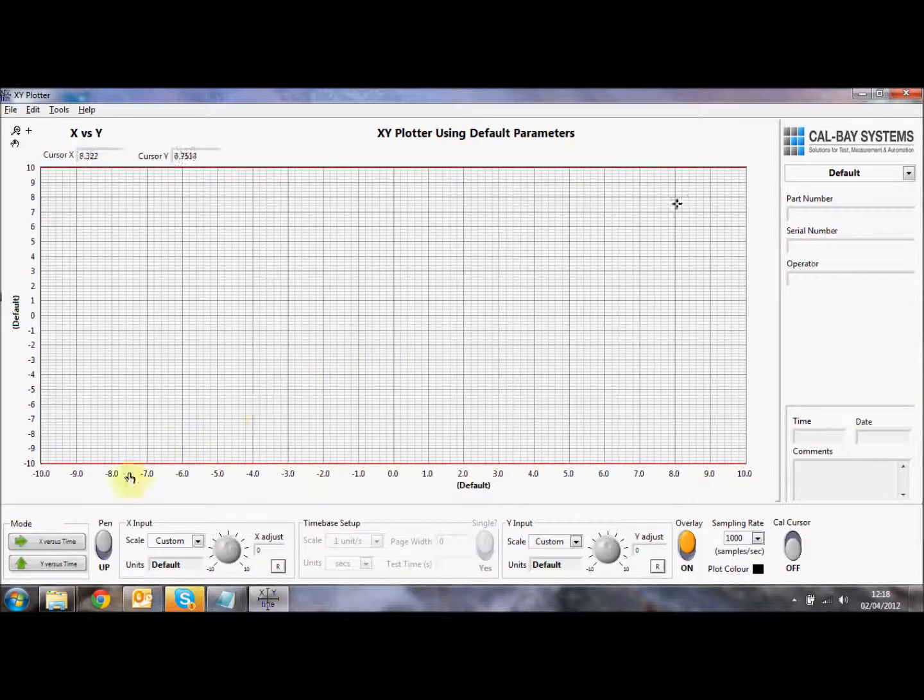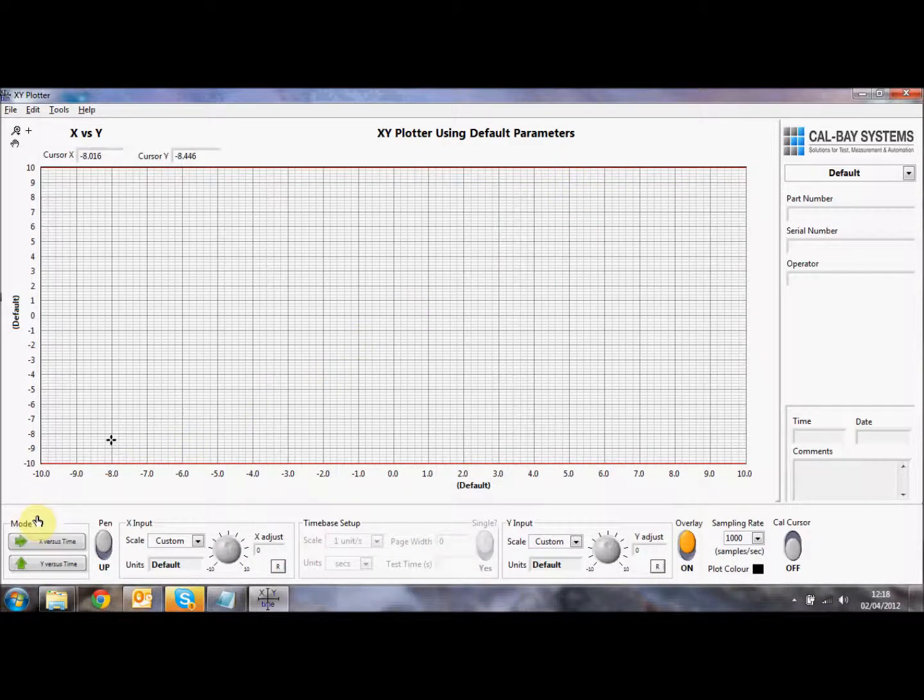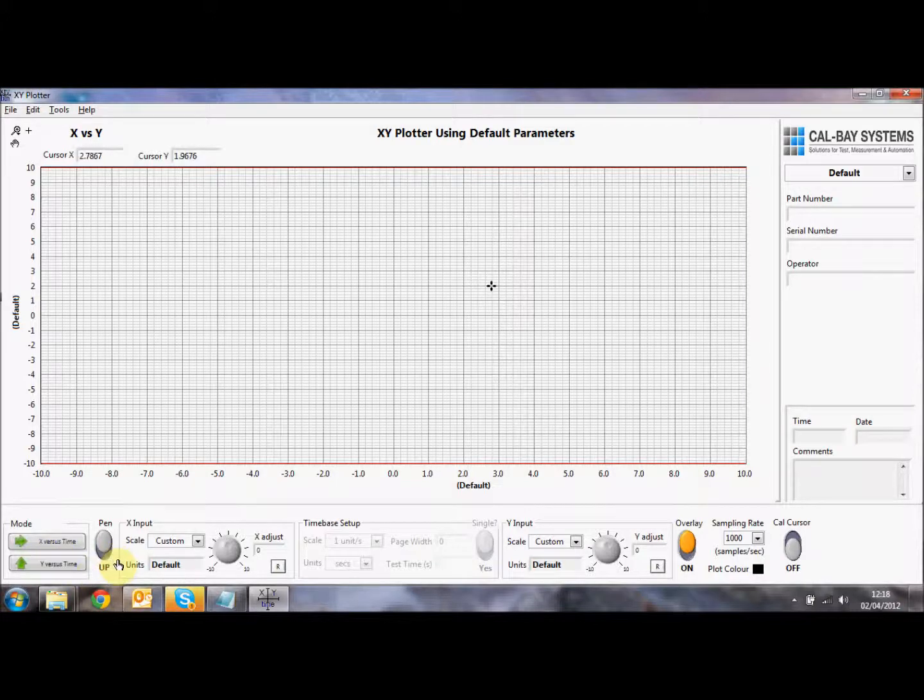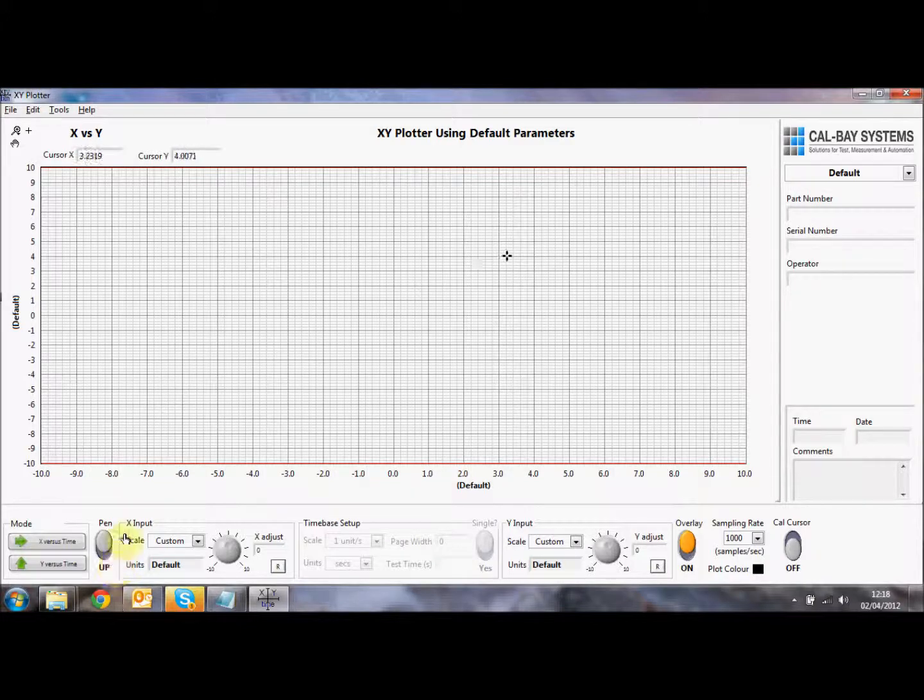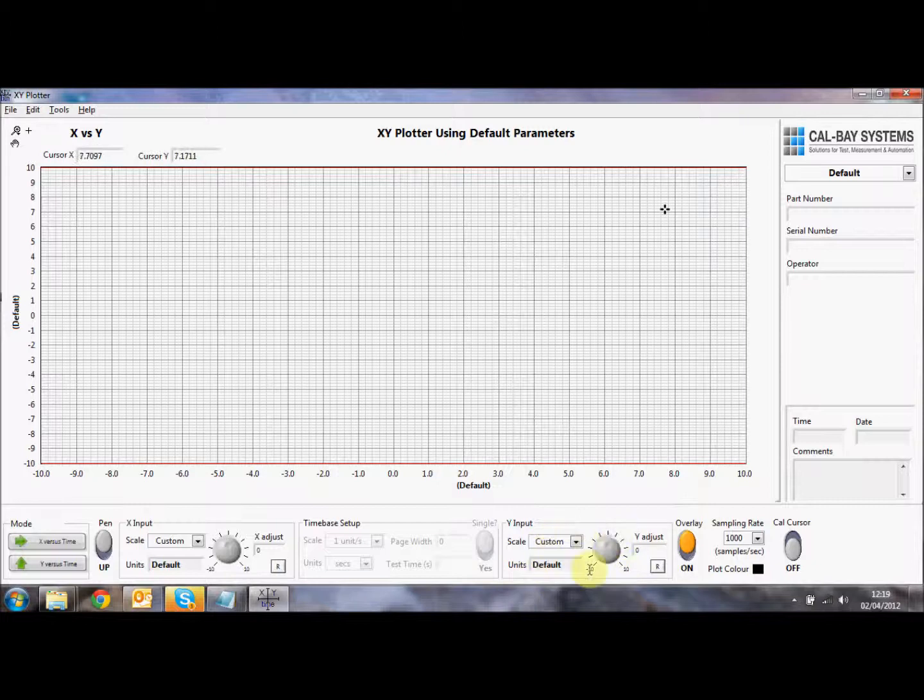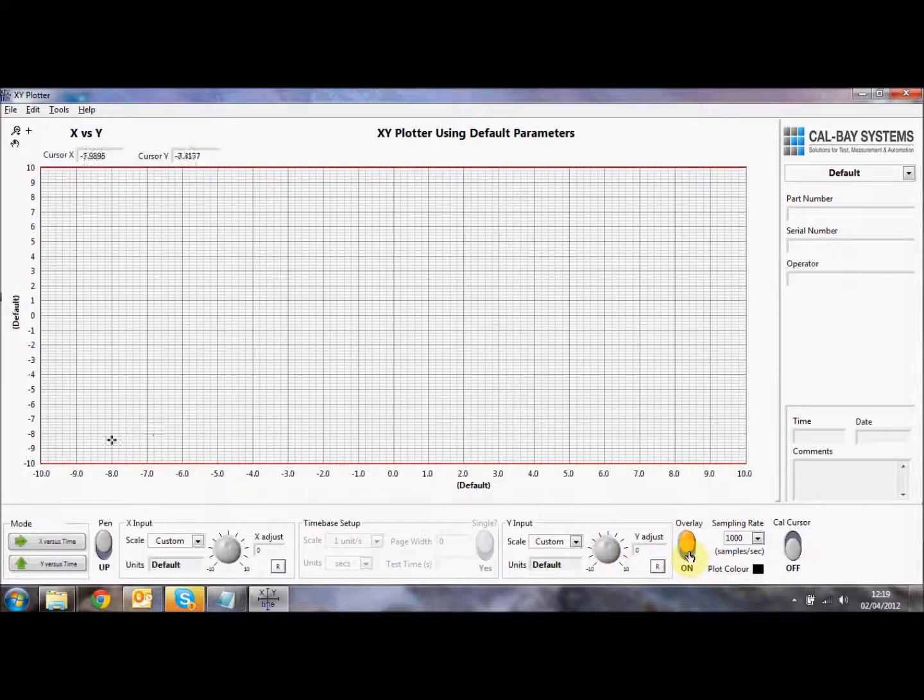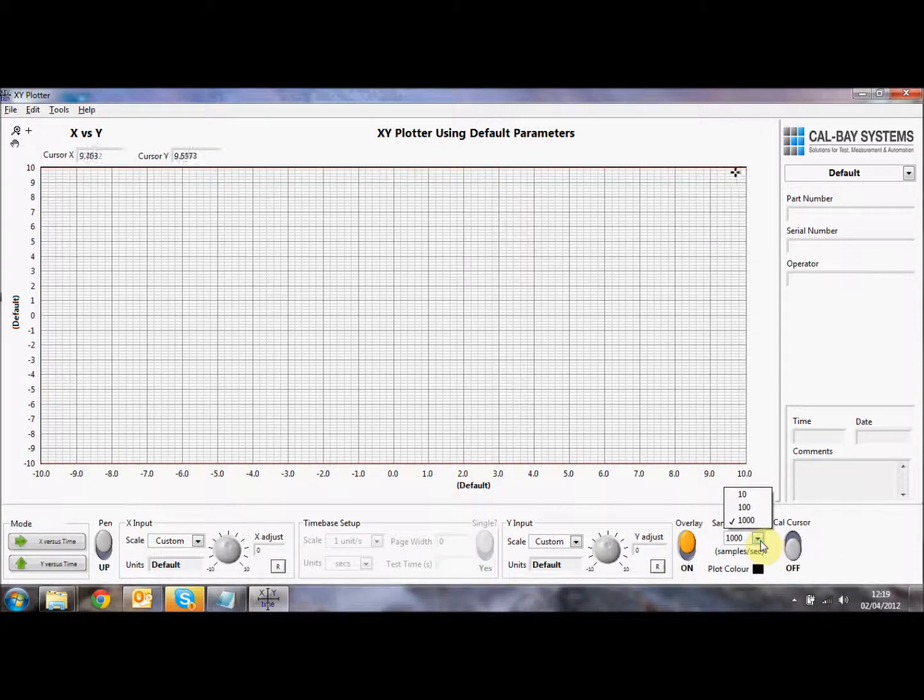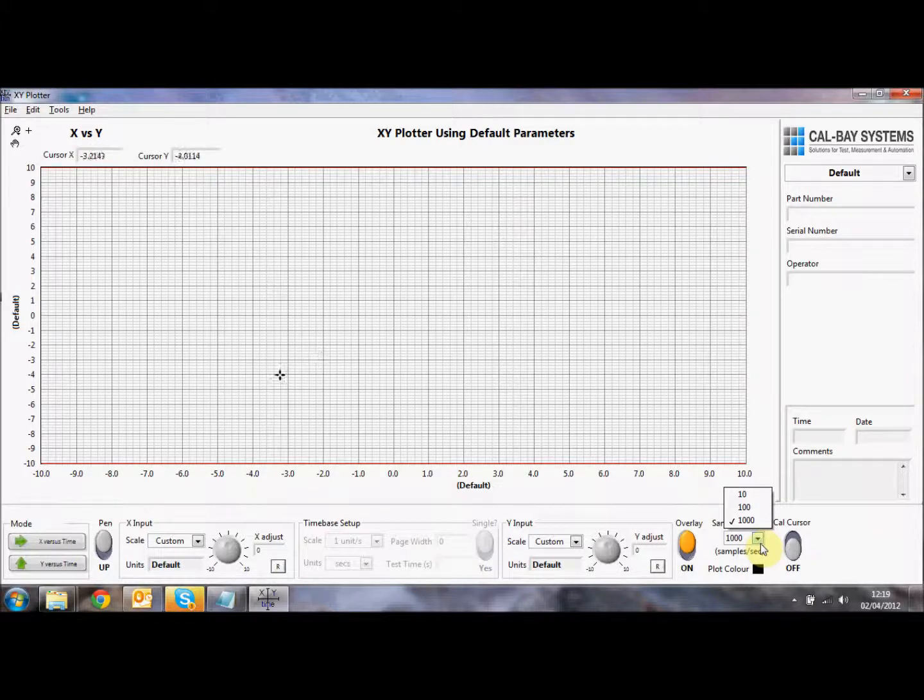Along the bottom of the XY plotter software, you've got controls. So we have a mode function, so we can select X or Y versus time. We're currently in X versus Y. We have probably the most important button, which is the pen up and pen down button, which we start collecting data and saving data as a log file. We can change our scaling of the X input and the Y input here. We have an overlay function. I'll explain that shortly. We can change the sample rate of the board.